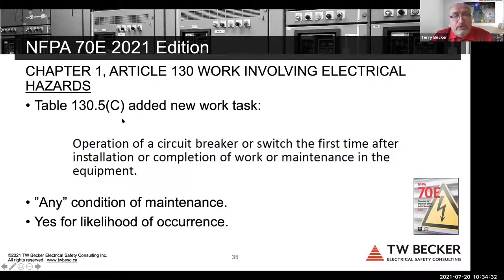So in Table 130.5C or Z462 Table 2, this was added as a new work task. And it's opening a circuit breaker switch the first time after installation or completion of work or maintenance in the equipment. And then the condition of maintenance is any, and the likelihood is yes. So greenfield, brand new, commissioning contractor, they should wear arc flash PPE when they open or close that circuit breaker for the first time in commissioning or after significant maintenance.